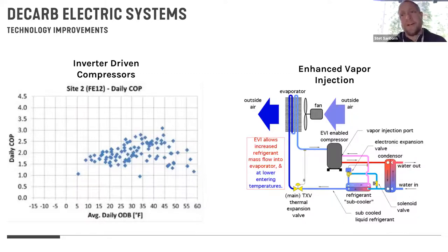So we see this as a really advantageous technology for cold climates. And there's a couple companies that are making these that are working in ASHRAE climate zone 7, the northern tip of Minnesota, but also good swaths of Canada. And they're working quite well with COPs north of 2, 2.5. And then as the temperature comes up into what I would consider okay to be outside, those COPs are fantastic.